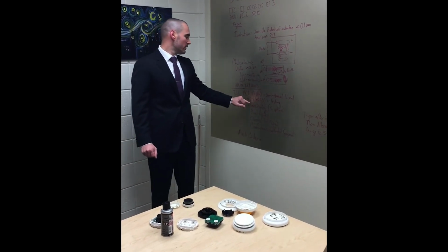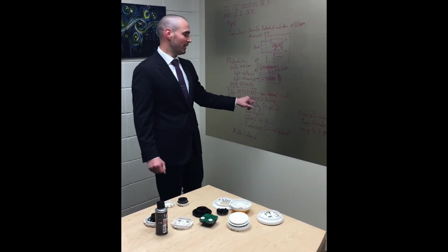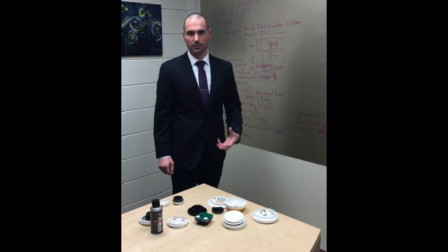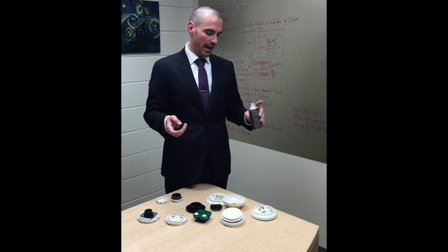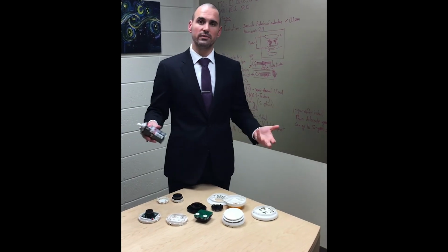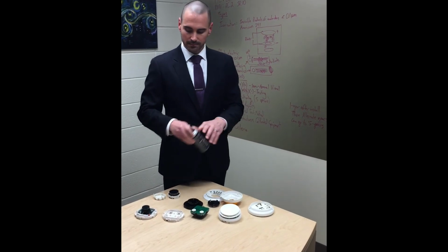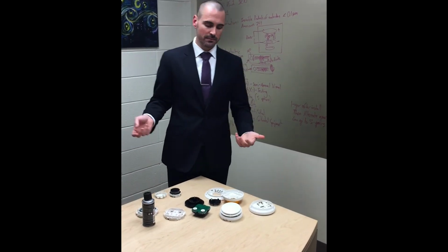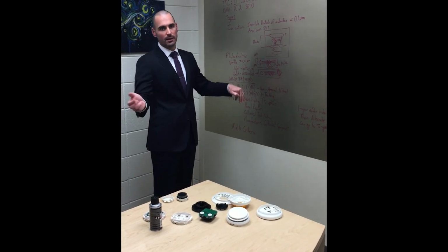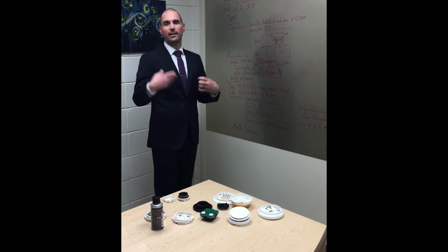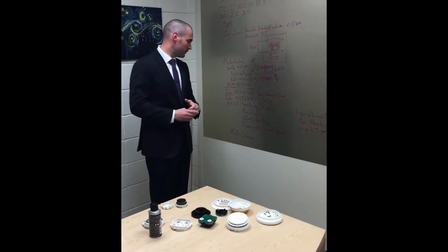Table 14.3.1(1), that's a mouthful, is the actual testing requirements for smoke detectors. That's where it says you actually have to spray smoke. We don't have the tool with us, I could show you guys, but you spray smoke into the smoke head and make sure that it physically activates. So don't use a magnet. We've said that a few other times. Magnets can only be used after you've tested the functionality of the smoke detector.